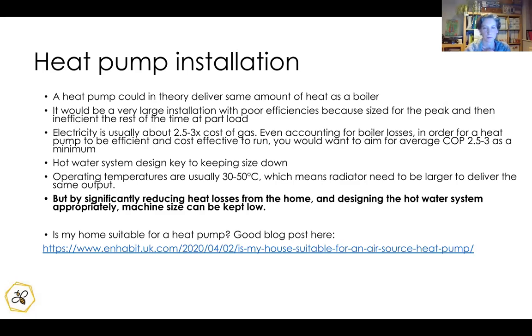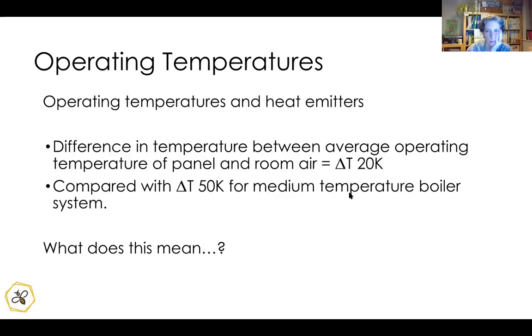The Tipperary Energy Agency did extensive testing on different radiator types, including underfloor heating, and found it wasn't necessary to have underfloor heating. You might need to oversize radiators slightly but not loads. Newer radiators may tolerate the change, while older ones full of gunk or near end of life might need replacing. The key point is the difference in operating temperature means radiators need to be considered carefully. This is about thinking of the home as a system rather than expecting powerful on-demand heat.